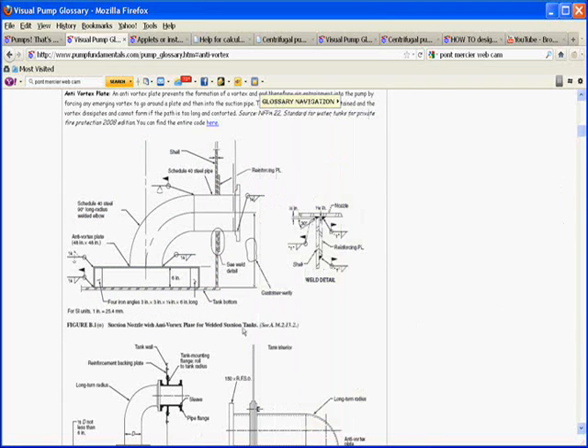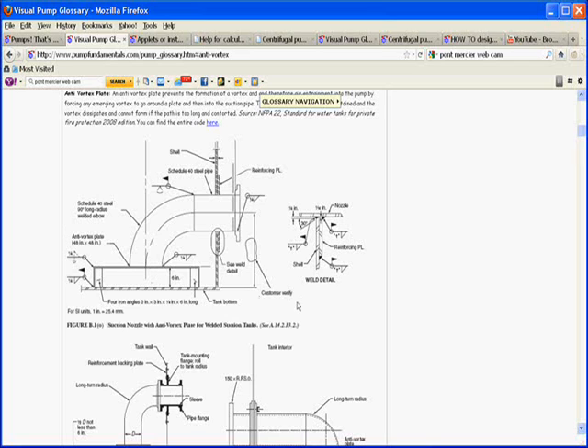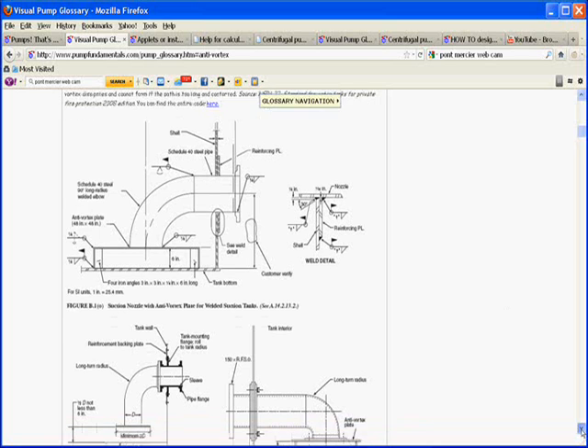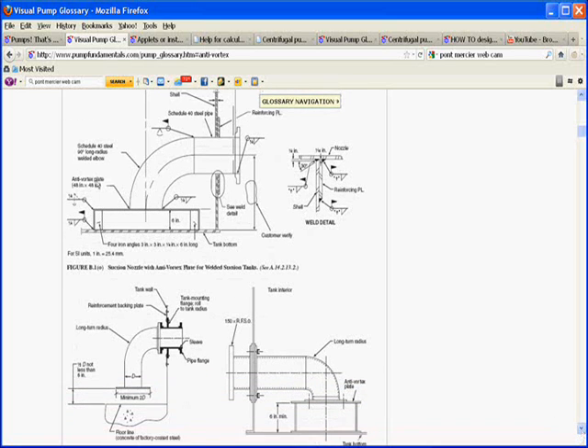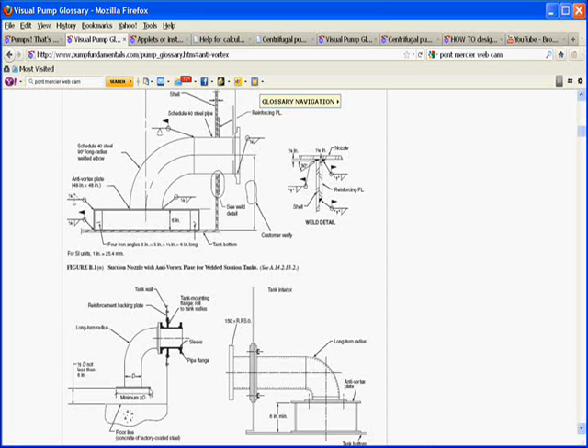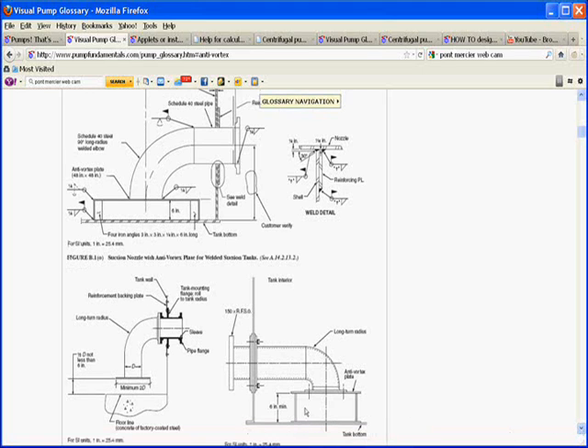If we put a plate on the suction pipe, we're going to force the liquid to come around quite a bit more before it gets into the suction, and that will probably stop that formation from happening because the vortex just doesn't have enough energy to get around and into the suction pipe. These are different styles of suction plates. Here's a very simple one where you just have a plate here extending basically the diameter of the pipe to twice its diameter, and this makes it difficult for the vortex to form. And here's another style here.